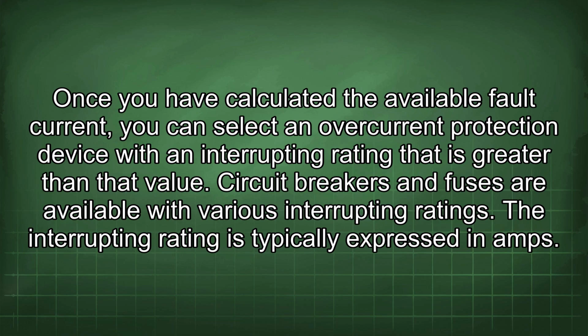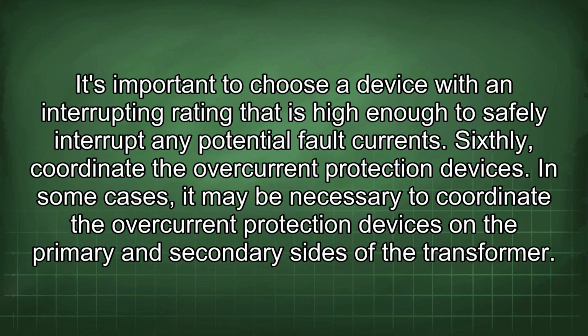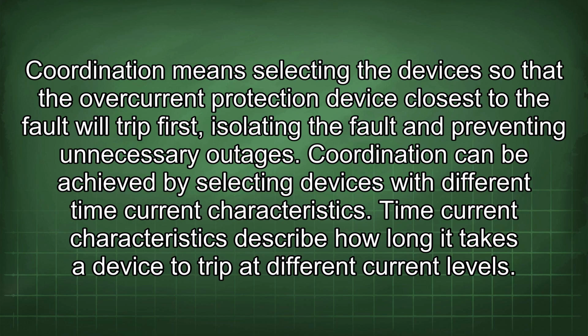Circuit breakers and fuses are available with various interrupting ratings. The interrupting rating is typically expressed in amps. It's important to choose a device with an interrupting rating that is high enough to safely interrupt any potential fault currents. Sixthly, coordinate the overcurrent protection devices. In some cases, it may be necessary to coordinate the overcurrent protection devices on the primary and secondary sides of the transformer. Coordination means selecting the devices so that the overcurrent protection device closest to the fault will trip first, isolating the fault and preventing unnecessary outages.